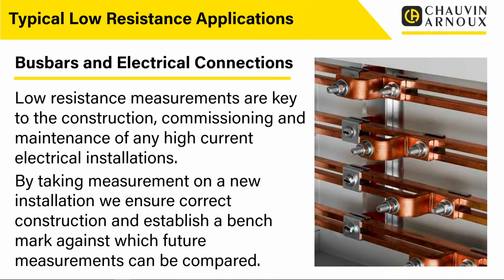So when we're creating these connections, it's good practice. In fact, it's pretty much essential that we check these joints with something like a micro-ohmmeter to make sure that we have got those correct in the first place. And then if we're doing some fault finding or maintenance later on, again, we can return to that and identify problems with the installation by comparing to those values that we achieved in the first place.